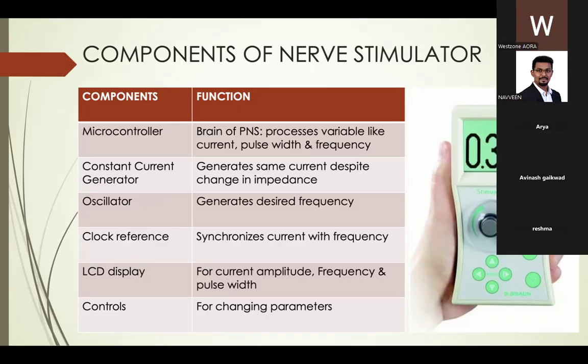frequency. And it has an LCD display for the current amplitude, frequency, and the pulse width, and the controls for changing the parameters. As you can see in the image, the 0.3 milliamperes is the set current. And this 0.1 millisecond is the pulse width or the chronaxy which has been set. And 2 hertz is the frequency, and 1 kilo ohm is the resistance which is offered by the tissues to the needle.